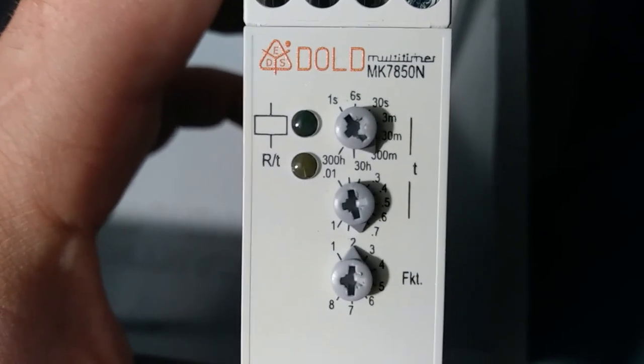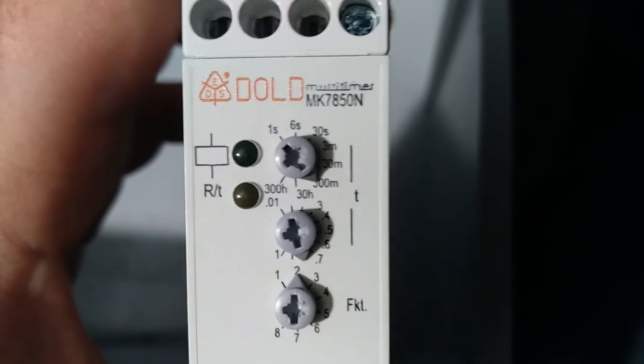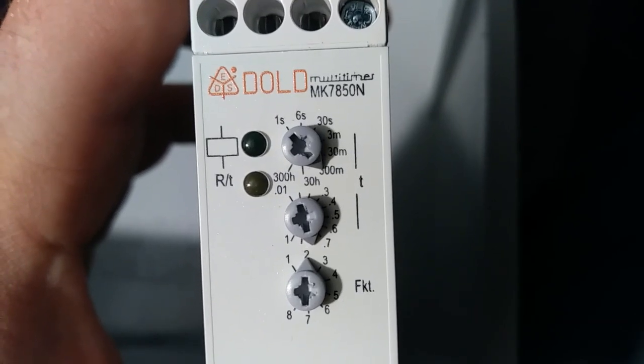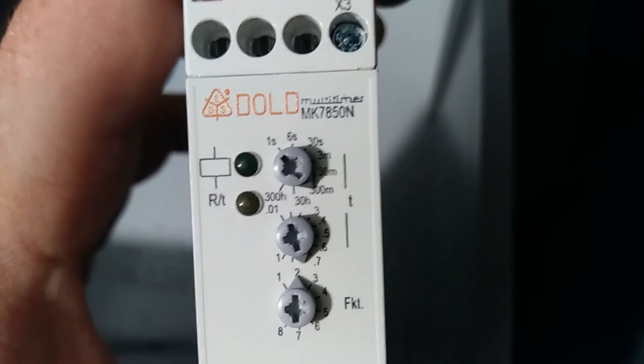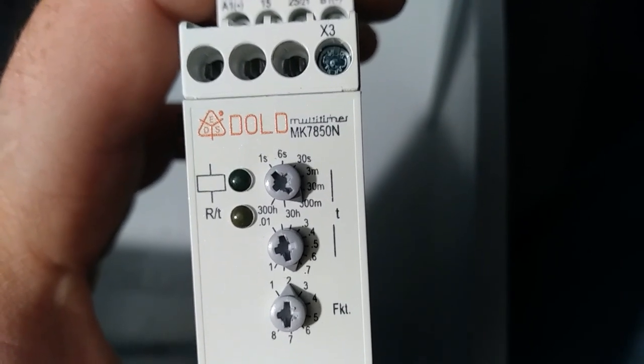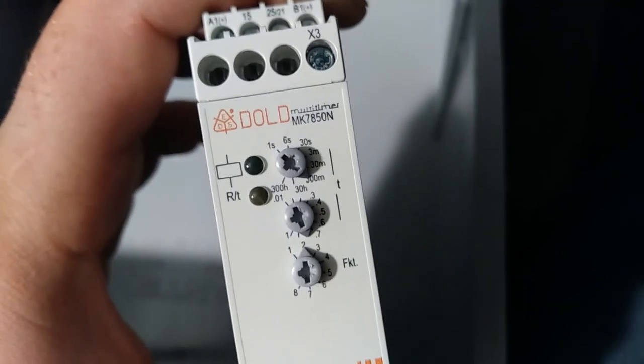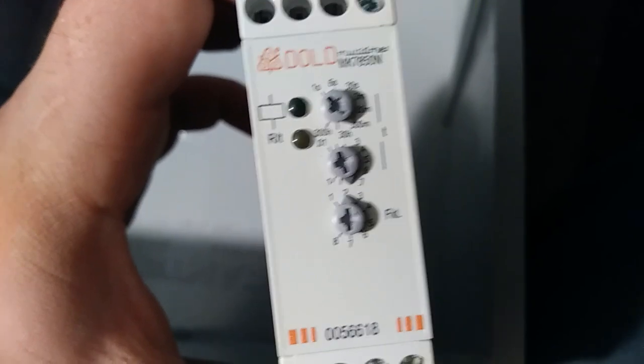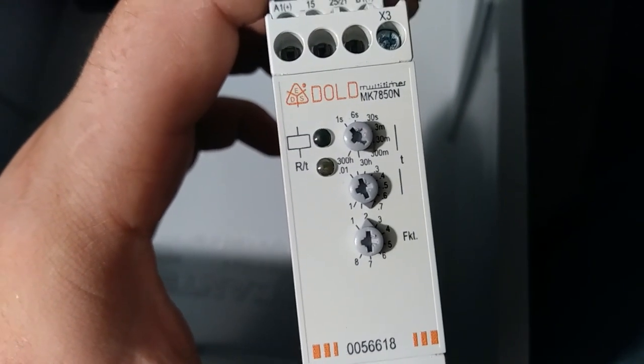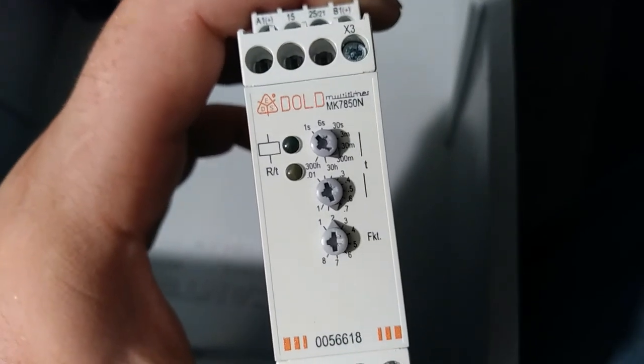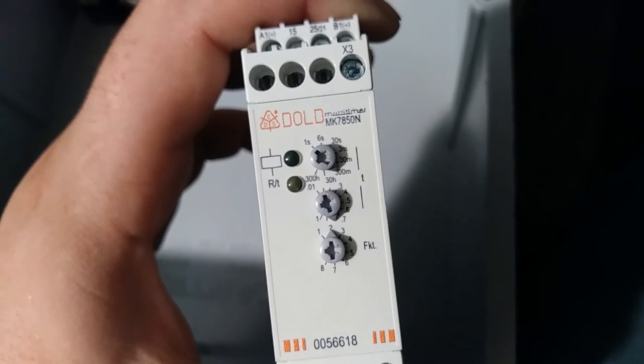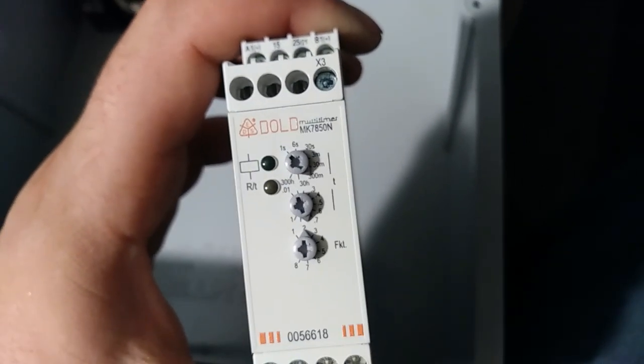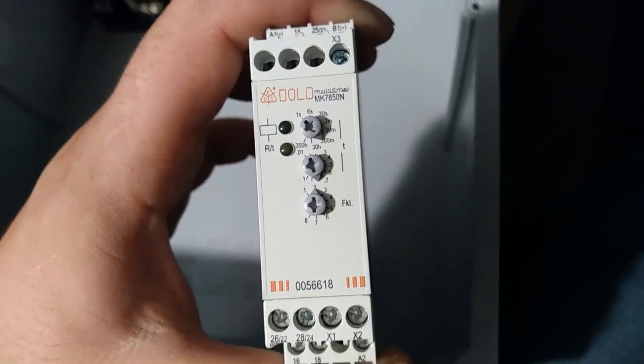You see 0.01s is all the way over there. And then, yeah, 0.01, 0.1, 0.2 are the blank. Yeah, you have 0.01, and then the next one is 0.1, and then the next one is 0.2. And then down here, you have 0.8 and 0.9, and then 1 being the full range. So, again, 0.8 of 300 should be four hours. 0.8 of 300 minutes should be four hours, if I did my math correctly. So, that should be that. I'll set both of them to that, and that should be all the setup we need to do. And I'll find some kind of way to test it as well.